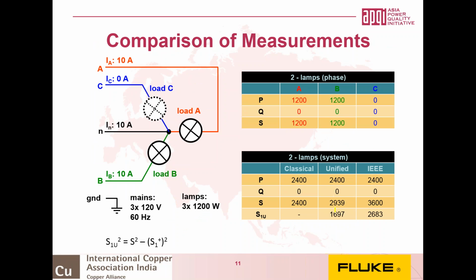We can see that here. And now the difference goes into a larger value of unbalanced apparent power. And the unified method calculates the unbalanced apparent power as 1,697 VA. And this is because the 3-phase generator is determined to deliver 3-phase power with same phase voltage and same currents. And because of that, when one lamp fails, the 10 amps that's in the phase drops to 0, and instead you suddenly have 10 amps flowing in neutral, which is a bit of a surprise. The fact of the neutral flowing is in itself a sign that not all is well. So neutral is a reference point, is not supposed to carry current except when there's a fault.